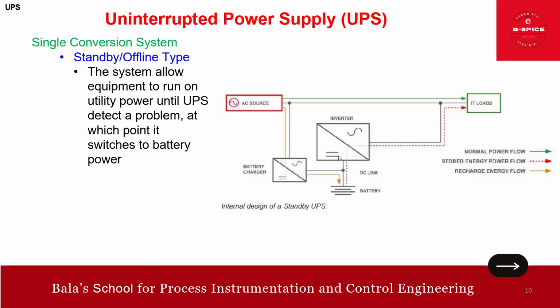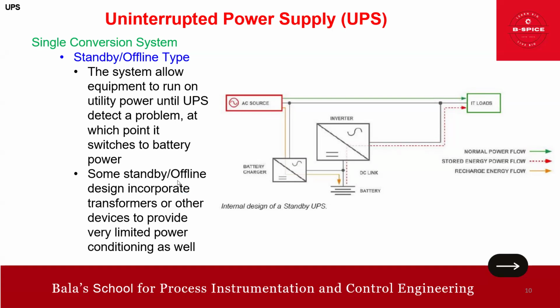Here's the same diagram: source, battery, inverter, and IT load. The system allows the equipment to run on utility power until the UPS detects a problem, at which point it switches to battery mode. This is standby, it stays in standby until it detects a power system failure on the input side. Some standby offline designs incorporate transformers or other devices to provide very limited power conditioning as well; some types provide a transformer side which we are not discussing here in detail. So this is the standby offline type.